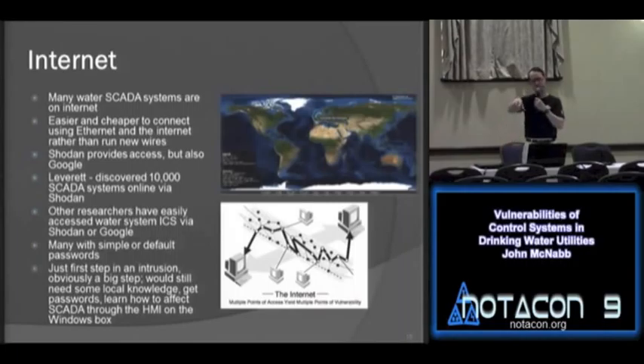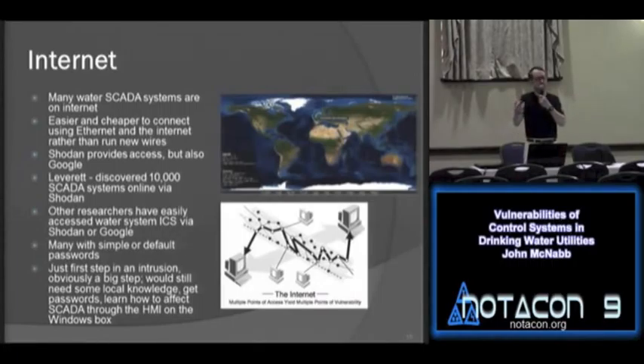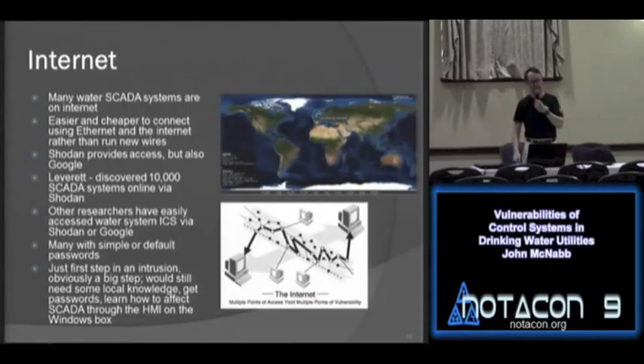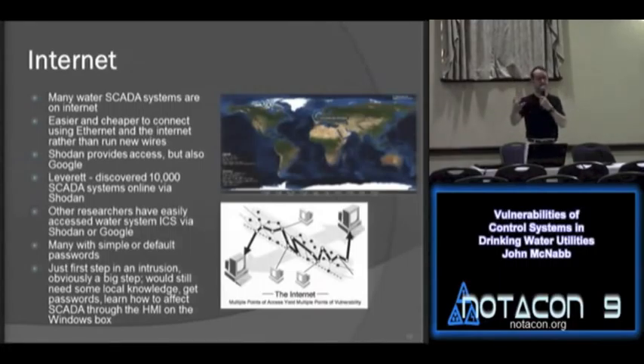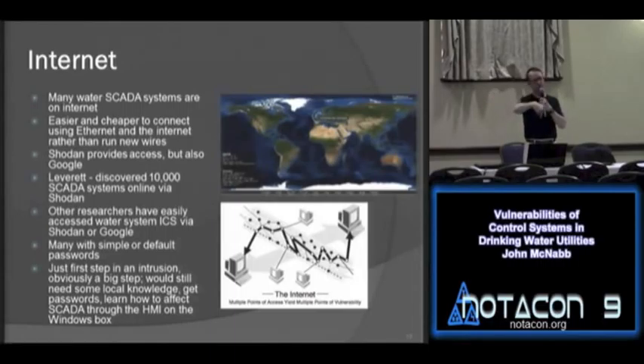A lot of utilities will also say their business network isn't connected to the SCADA network — and they're usually wrong. It's just too convenient to punch a few buttons in the business office and get SCADA information for your report or updates or planning. When I was running my plant and asked our manager 'are we on the internet?' he said no — but I checked and one of our pumping stations had an IP address I could get from my home computer. And when I asked if we were connected to the office system, he said no — but they were.